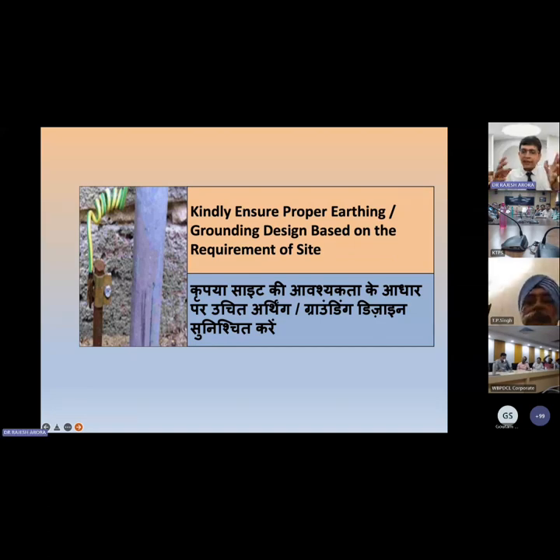You have to understand equipotential bonding. You have to understand bonding and earthing. You have to understand the proper size of the earthing conductor. You have to understand the proper size of electrode required. And I always say in my seminars and videos, and I would like to reiterate, that OLOE should be the takeaway of today's webinar. OLOE, one location, one earthing, should be the fundamental rule.